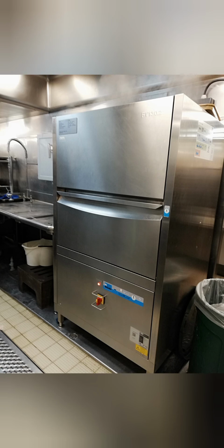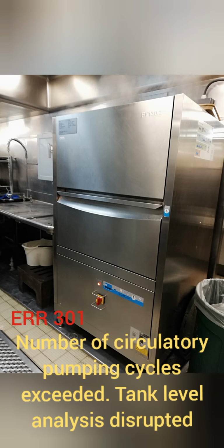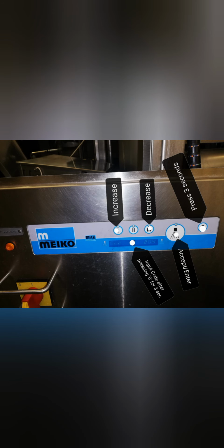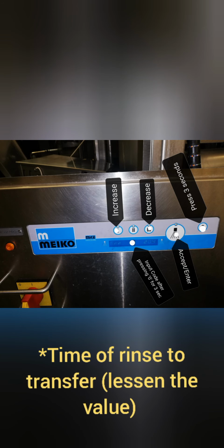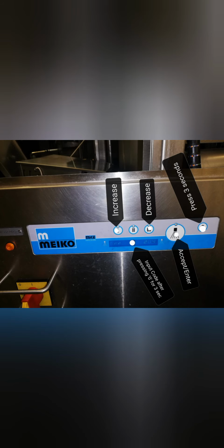But the errors don't stop there, because in the middle of the transfer, error 301 appears, referring to the number of circulatory pumping cycles exceeded, tank level analysis disrupted. So the last thing I changed was the rinse to transfer time. I lessened the time value to the factory setting, and everything just went well. So that's it. We're fortunate because after all of it, it works.